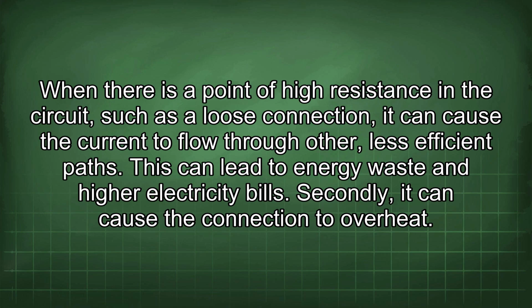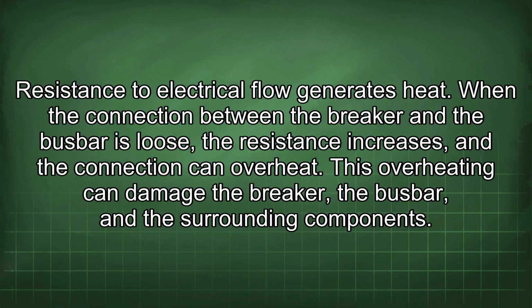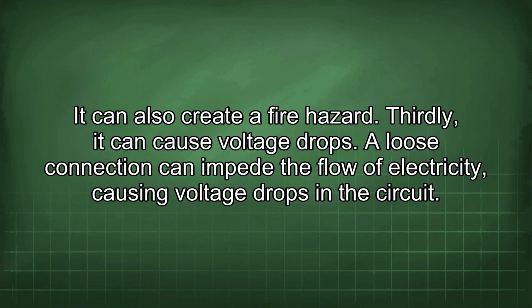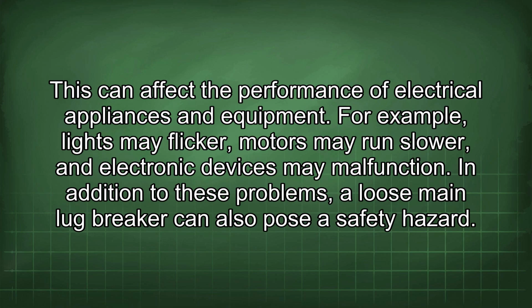Secondly, it can cause the connection to overheat. Resistance to electrical flow generates heat. When the connection between the breaker and the busbar is loose, the resistance increases and the connection can overheat. This overheating can damage the breaker, the busbar, and the surrounding components. It can also create a fire hazard. Thirdly, it can cause voltage drops. A loose connection can impede the flow of electricity, causing voltage drops in the circuit. This can affect the performance of electrical appliances and equipment. For example, lights may flicker, motors may run slower, and electronic devices may malfunction.